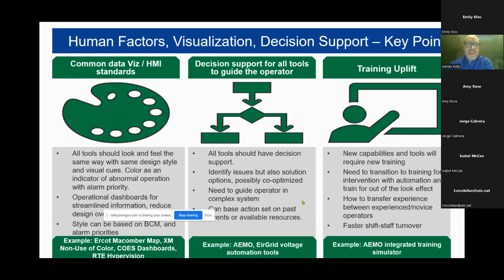Lastly, we're thinking about the human factors elements and decision support. What we're thinking about here is common data visualization and HMI standards. So having the same operational technology toolkit colored in the same way, indicating color using abnormal indications, operational dashboards. So we spoke about hypervision and a single streamlined dashboard for system operation. Again, COES will talk about this with their very advanced PI dashboards. And also want to call out XM in Colombia, who spoke recently to G-PST, who really advanced the field with redesigning their control center interfaces with an emphasis on color minimization. Hypervision is a concept developed by RTE in France, and also the ERCOT famous Macomber map in their control center that shows various different layers and systems based on what's up.